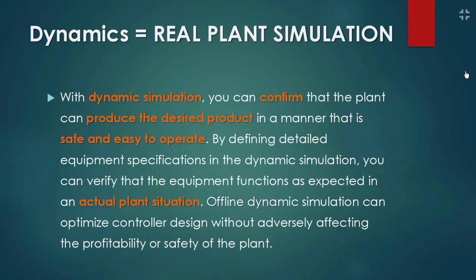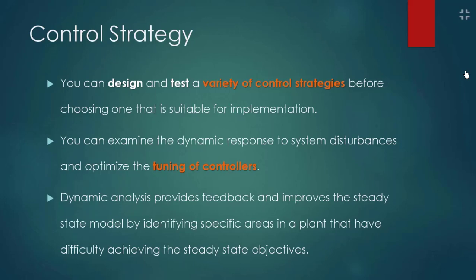The main advantage of dynamics is that if you have a plant that's already running and you need to see the impact of changing the feed flow rate or changing the control strategy, you cannot do it online — meaning you cannot do it while running the plant. So you have to make a simulation of your case in HYSYS, defining all the control strategies to see how they will affect plant performance. For example, if you have a feedback control loop and need to study the impact of changing it from feedback to cascade, you can verify which is better or try another control loop. You simulate it in dynamics mode to see which gives better results and better response.